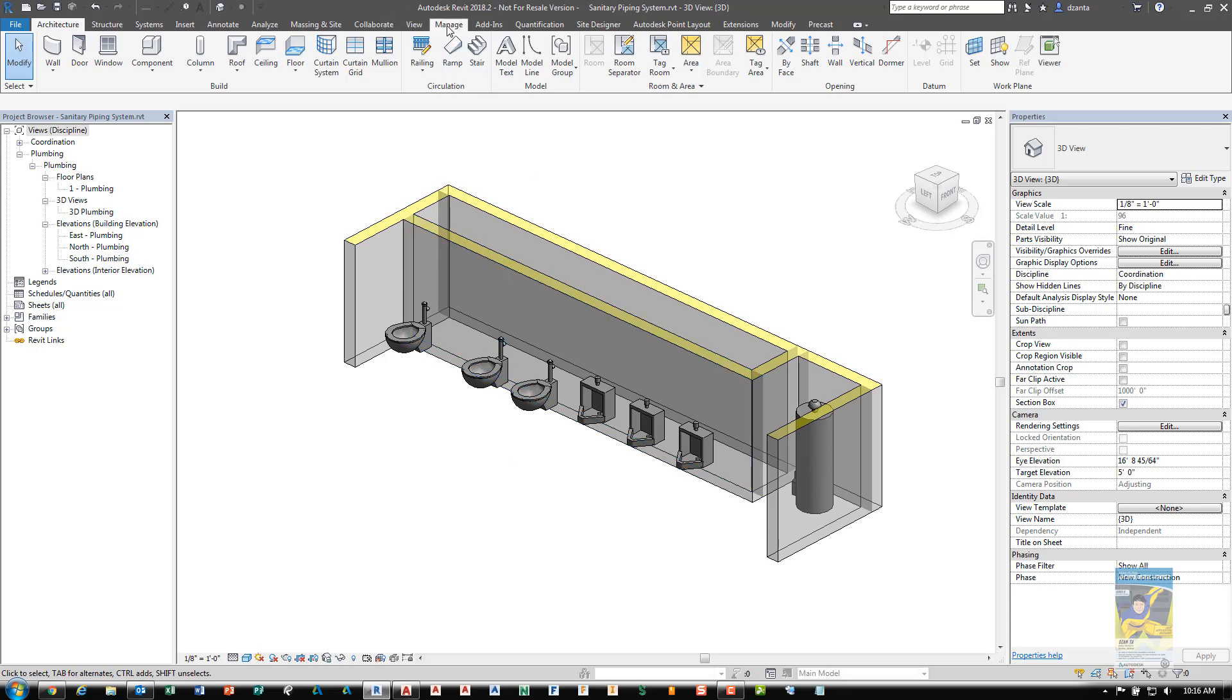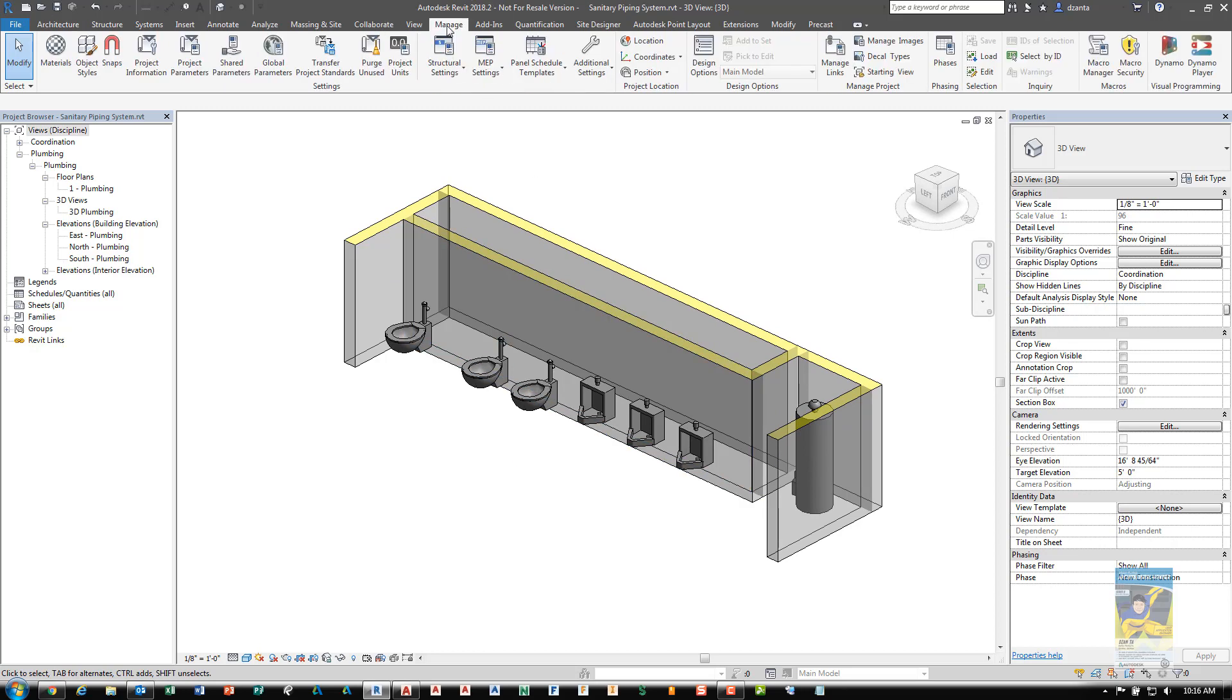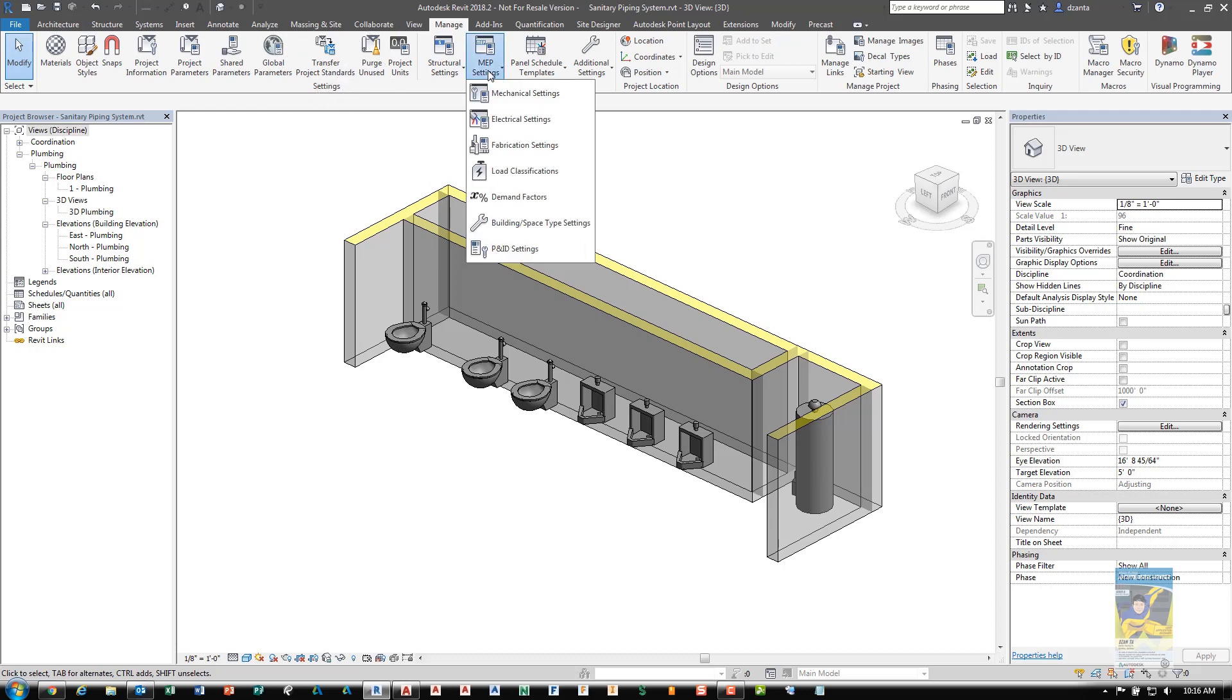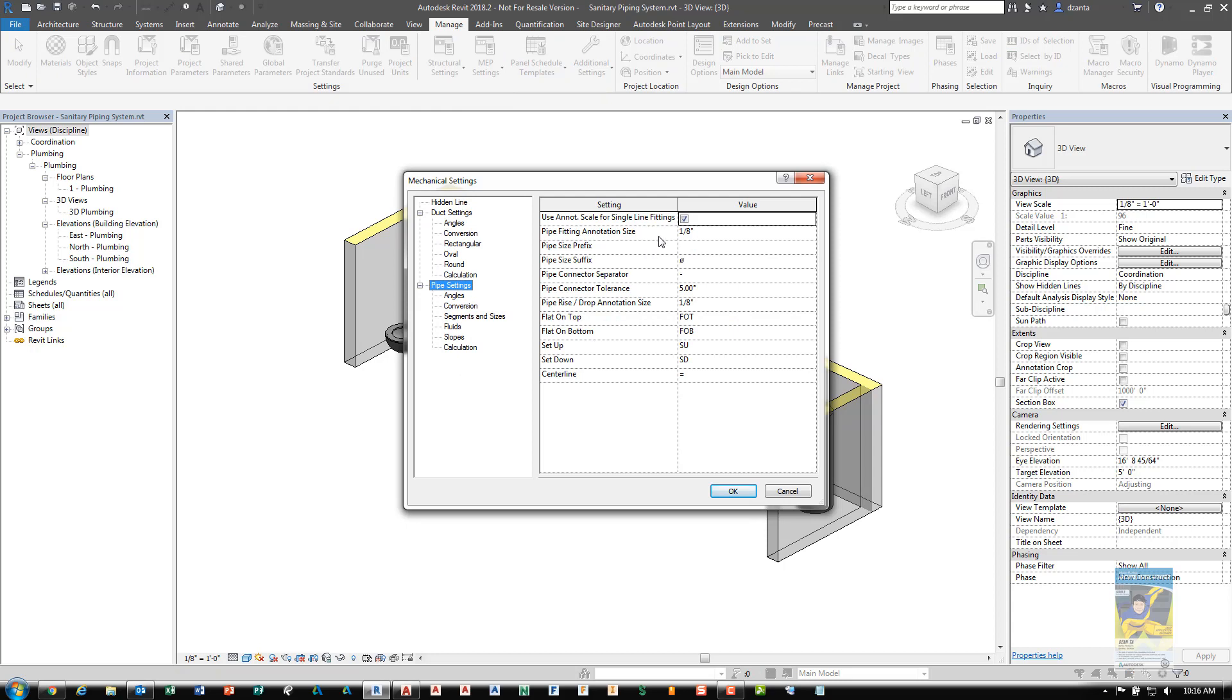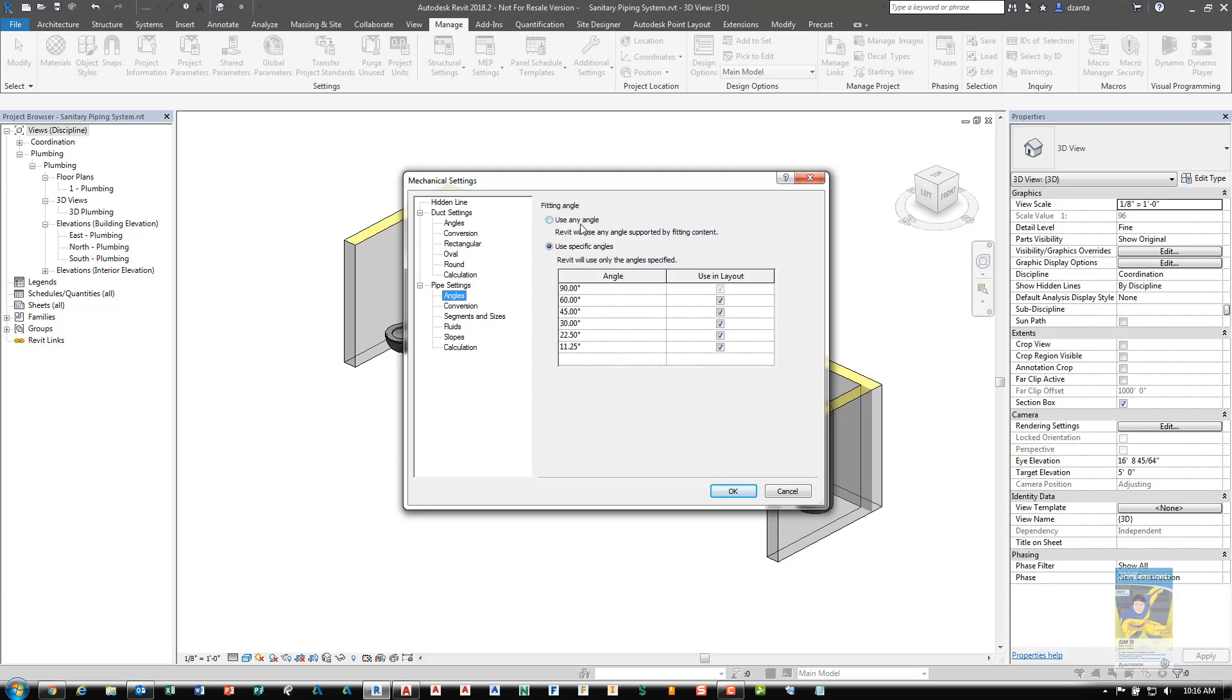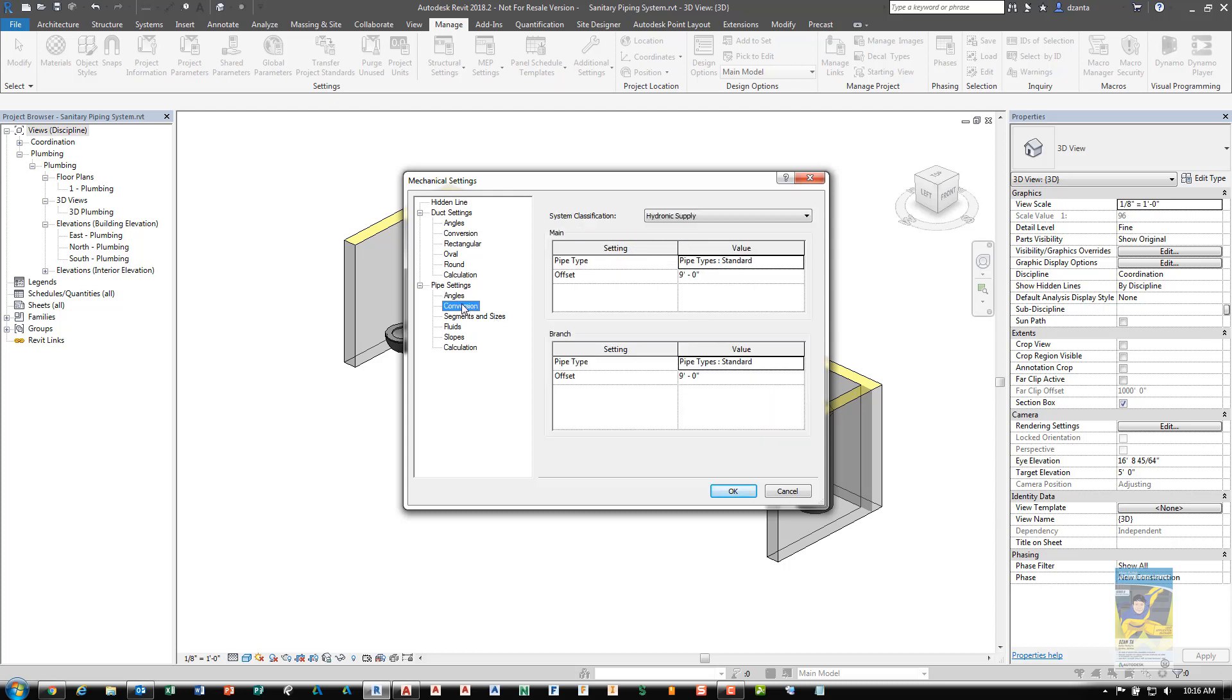Head over to the Settings panel and click under MEP Settings to make the necessary default settings. Under Mechanical Settings I have Pipe Settings with content such as how tolerances are set up, the percentage for rise drop annotation size, and angles. By default Revit's template file will use any angle. You can force it to use specific default angles like 90, 60, 45 degrees, things that make sense out of the box for a lot of types of fittings and accessories.